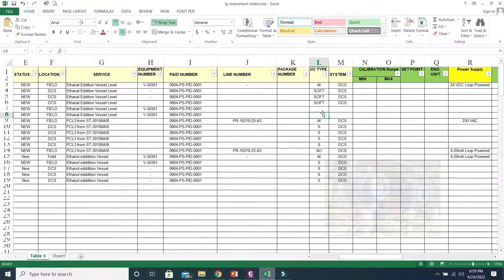Then IO type. For each and every tag we need to provide the IO type, whether it is a hard signal or a soft signal. Alarms are soft signals, but all the transmitters, all the control valve positioner outputs, all the on-off valves and switches are hard IOs. Based on the PNID review or our knowledge, we can provide the IO type. We will also discuss this IO type in the IO list documents. Just like a pressure transmitter is an analog input, so for all the pressure transmitters we will mention AI. A control valve is an analog output. Alarm is a soft signal, so we can mention S for soft, AI for analog input, AO for analog output, DI for digital input, DO for digital output. So this is the IO type.